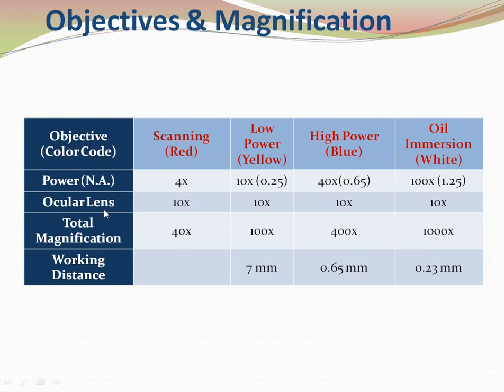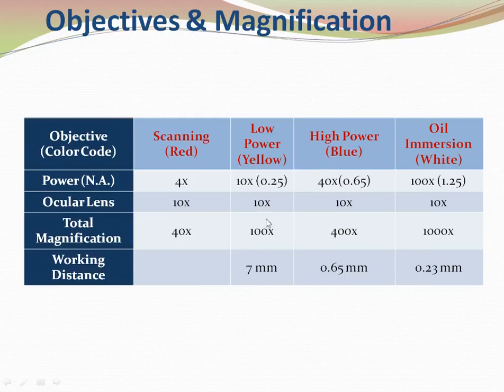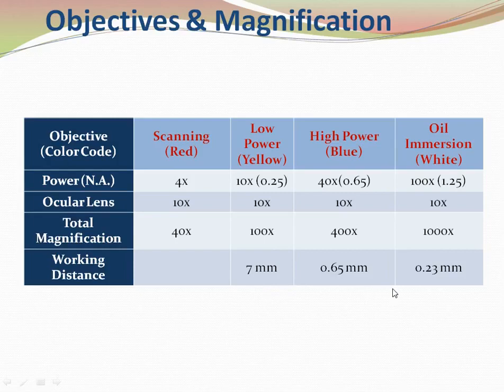Magnification power of different objectives: the scanning objective is 4x; the ocular lens is 10x for all. Total magnification is objective multiplied by eyepiece: scanning gives 40x, low power 10x objective gives 100x, high power 40x gives 400x, and oil immersion 100x gives 1000x. Working distance decreases as magnification increases. Knowing the working distance helps in focusing the specimen quickly and easily.